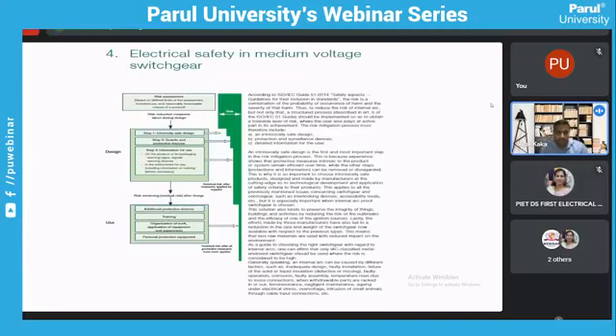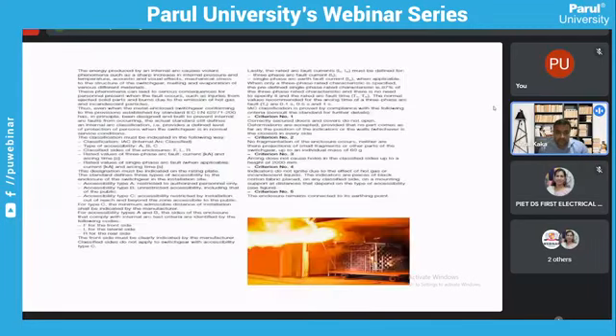So coming to internal arc classification. Now, all our medium voltage switchgears are also defined as per accessibility, as per the classification of an IAC, right? So types A, B, and C are the accessibility levels, which we normally define. Type A is restricted to authorized personnel only. Type B is normal practice with unrestricted accessibility, including to the public. And type C is accessibility restricted by installation.